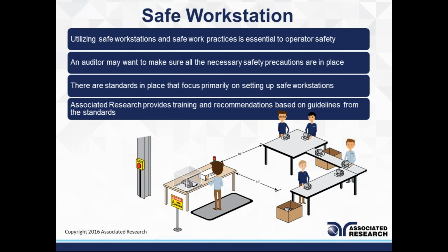One example is the picture shown at the bottom of the slide, showing a safe workstation setup, with minimum clearance distances between a test station and other people in the area and the facility. The operator is standing on a safety mat. The instrument being tested is inside an enclosure. There's an e-stop switch, warning signs, and a signal tower light. All these things are based right out of the safety standards, and it's very essential that all of us follow these recommendations, because if we are not following these properly, OSHA can write us up, and it has happened in the past.